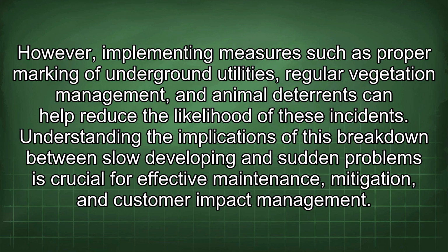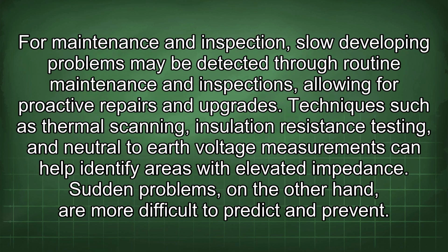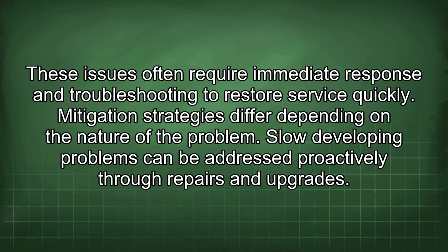likelihood of these incidents. Understanding the implications of this breakdown between slow-developing and sudden problems is crucial for effective maintenance, mitigation, and customer impact management. For maintenance and inspection, slow-developing problems may be detected through routine maintenance and inspections, allowing for proactive repairs and upgrades. Techniques such as thermal scanning, insulation resistance testing, and neutral-to-earth voltage measurements can help identify areas with elevated impedance. Sudden problems, on the other hand, are more difficult to predict and prevent. These issues often require immediate response and troubleshooting to restore service quickly.